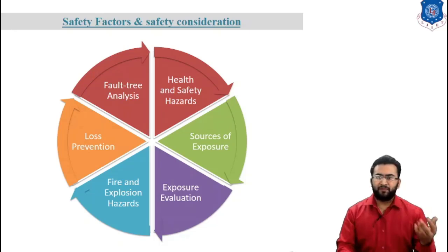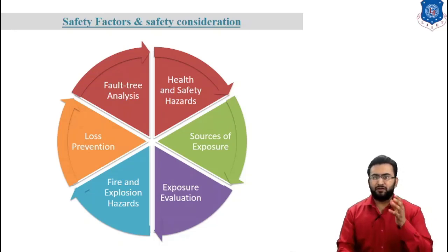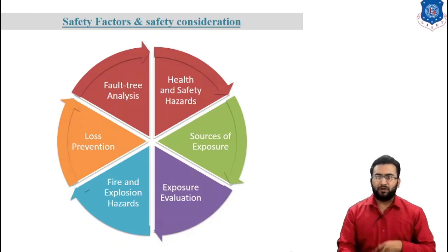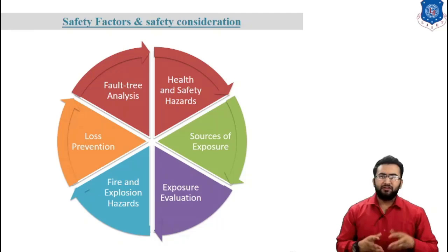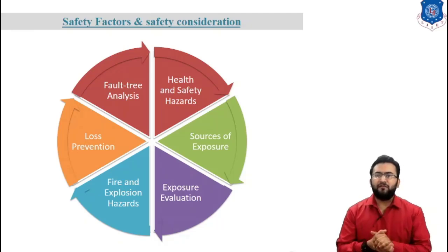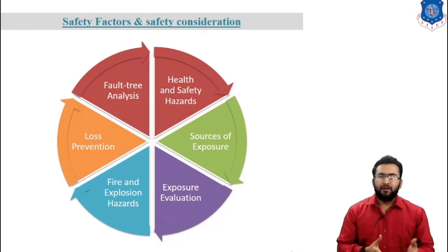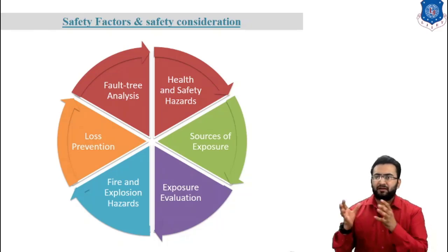Fouling which may occur during the operation should never be overlooked when the design safety factor is determined. Potential increase in capacity requirement is sometimes used as an excuse for applying a large safety factor. This practice can result in so much over-design that the process or equipment never has the opportunity to provide its economic value. In general design work, the magnitude of the safety factor is decided by economic or market consideration.